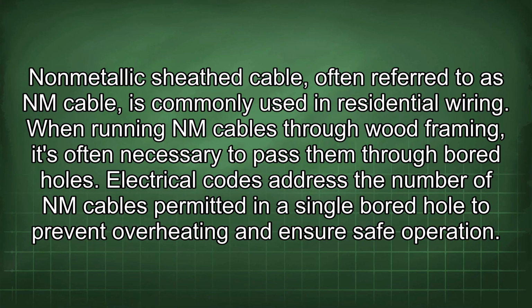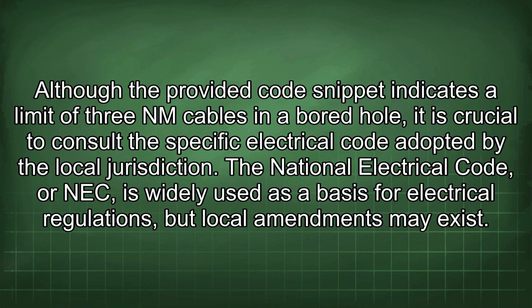Nonmetallic sheathed cable, often referred to as NM cable, is commonly used in residential wiring. When running NM cables through wood framing, it's often necessary to pass them through bored holes. Electrical codes address the number of NM cables permitted in a single bored hole to prevent overheating and ensure safe operation.